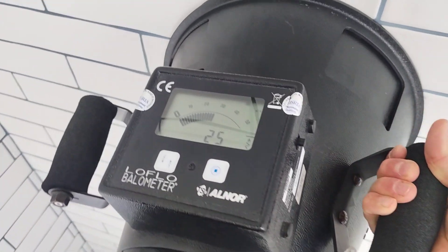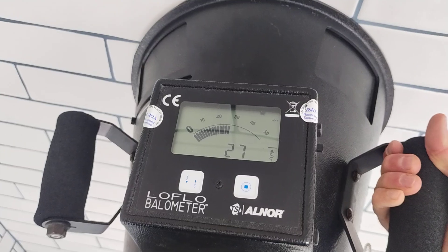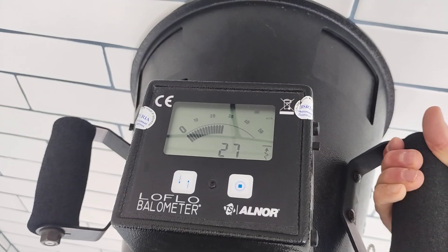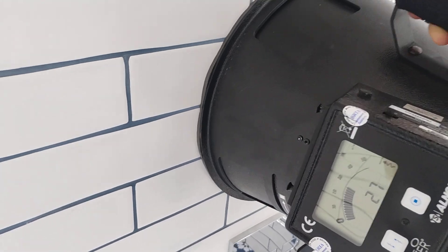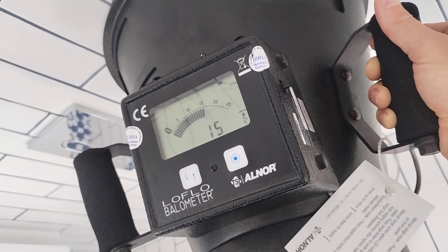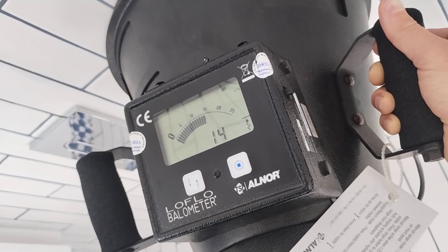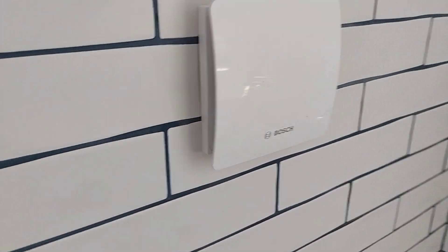The MVHR valve is currently running at 27 cubic metres per hour, and this noisy extractor fan is running at 15, 14 cubic metres per hour — so almost half — and it's so much louder and noisier than the MVHR system.